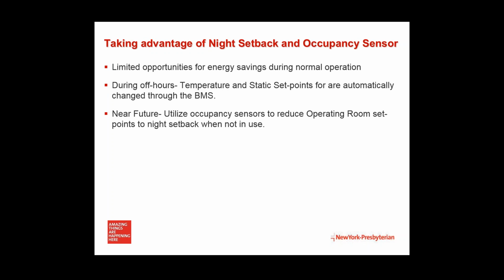So, taking advantage of night setback and occupancy. During normal operations, there are very minimal opportunities for energy savings. You maintain within the operating ranges, but you have to maintain your set points and compliance. The opportunities come during the off shifts when the operating rooms are not in use, as previously mentioned. The Allen Hospital utilizes a night setback feature where we adjust the temperature set points for energy savings. The adjustment of set points in turn reduces the output needed from the air handlers via mechanical cooling, heating, and CFM. Humidity and pressure sensors in the operating rooms verify that the rooms remain compliant to keep a sterile, safe environment. If emergency cases take place during these timeframes, a call would be placed to the engineering department that would disable the night setback feature. This process achieves significant savings, especially during the summer months when mechanical cooling drives energy costs to twice the average monthly budget during the rest of the year.